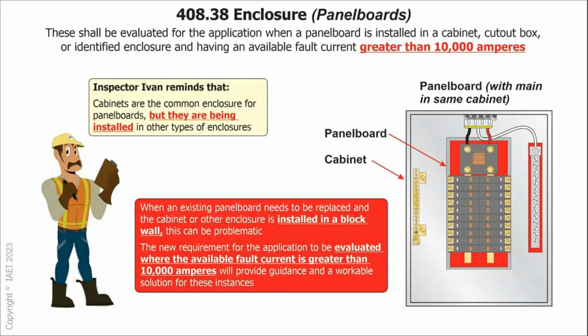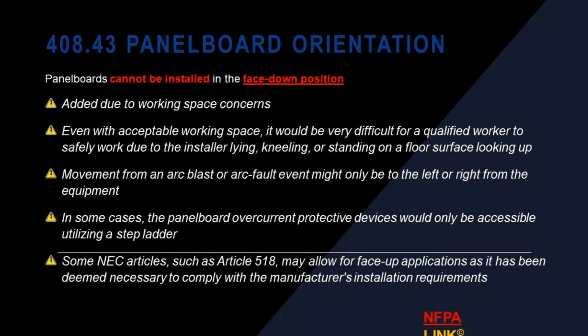Right? So here we go. Our 23 change. These shall be evaluated for the application when the panel board is installed in a cabinet, cutout box, or identified enclosure and having an available fault current of 10K or more. All right. Cabinets are the common enclosure for panel boards, but they are being installed in other types of enclosures. Okay. Make sense? Pretty straightforward. This is a code change, not going to be in your homework, just something we throw in there for you guys to see the code changes.